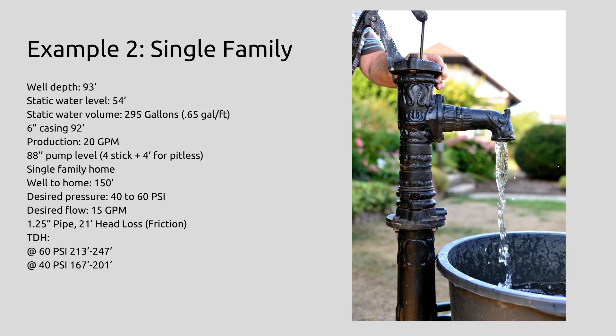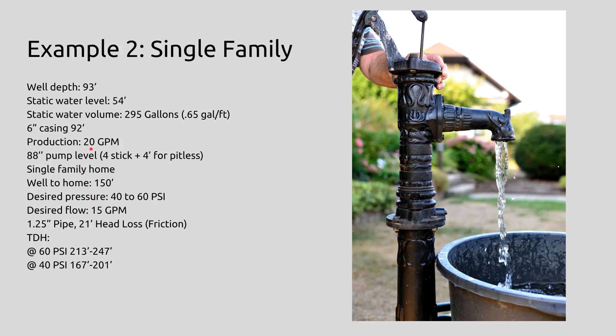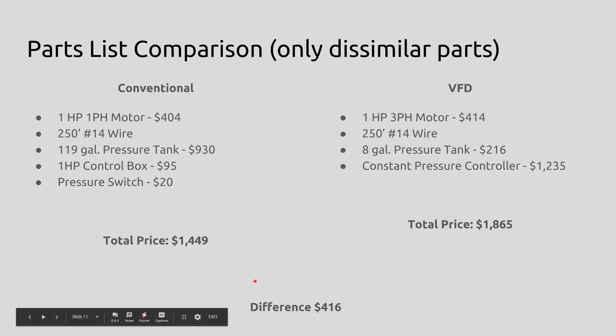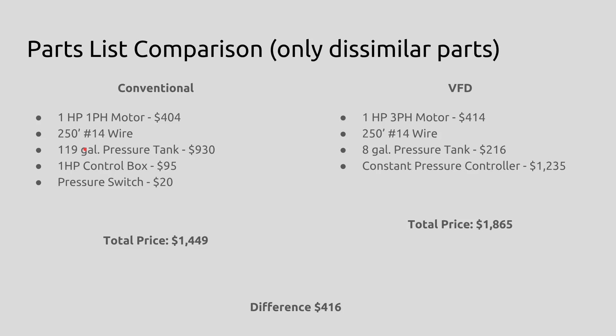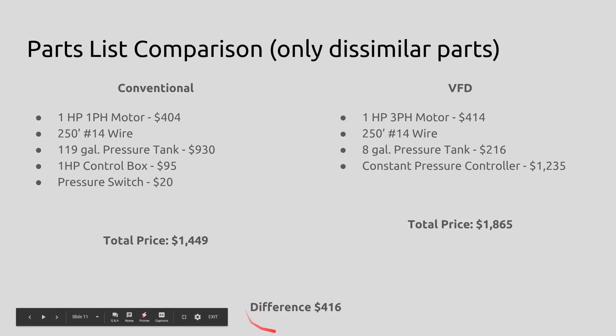Example two: well depth 93 feet — a pretty shallow one, because I felt it was going to be a much closer comparison. We've got a really shallow well at 93 feet with a static water level of 54 feet. Distance to home is 150 feet. We want 15 gallons per minute, and the well produces 20 gallons per minute, so we're definitely not at risk of exceeding that. With the dissimilar part comparison — the motor, and the wire is actually the same size on this one so I didn't put a number next to it. We've got a 119 gallon pressure tank versus an eight gallon. That's a big cost difference, as is the one horsepower control box versus the one horsepower constant pressure control box. Total price on the conventional: $1,449. Total price on the VFD: $1,865. The difference is in favor of the conventional system on this one.